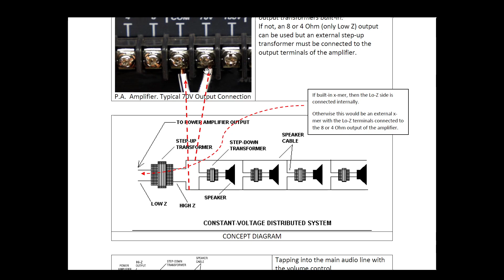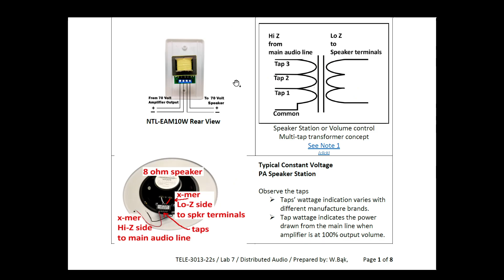If the system is cranked up to full volume with the signal still clear and not distorted, there is going to be 70 volt RMS on those two terminals, and the wattage taken from the main audio line is the wattage labeled on each tap of the transformer.